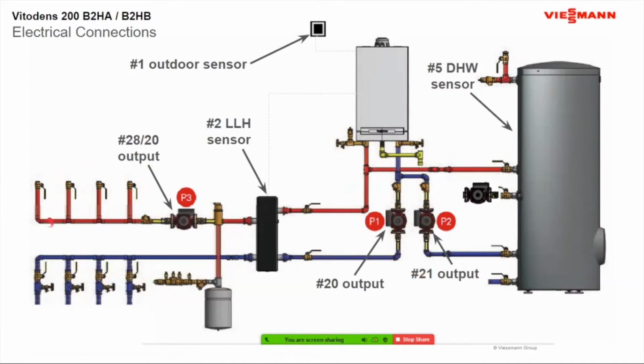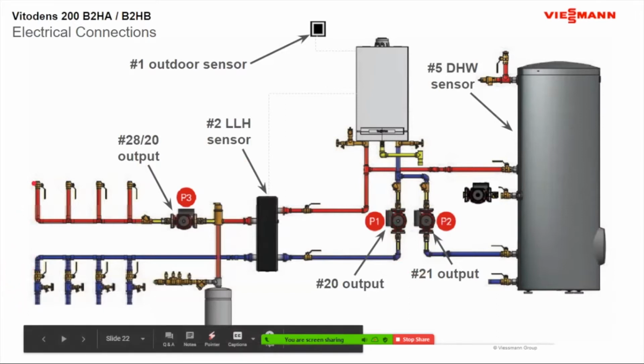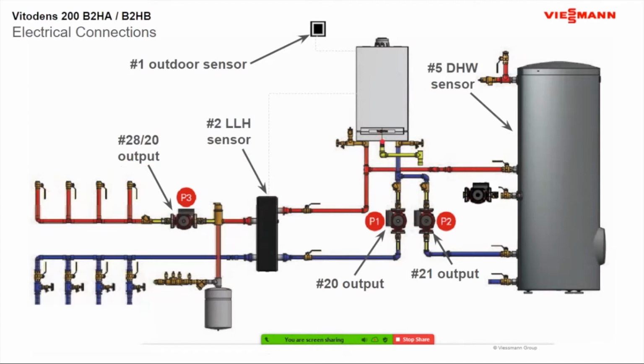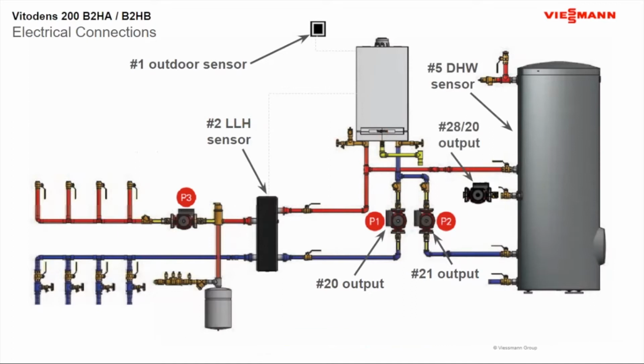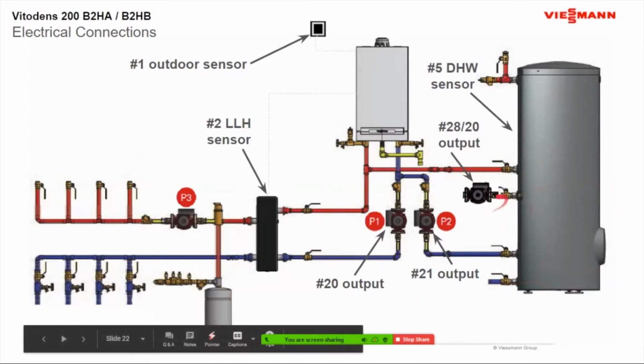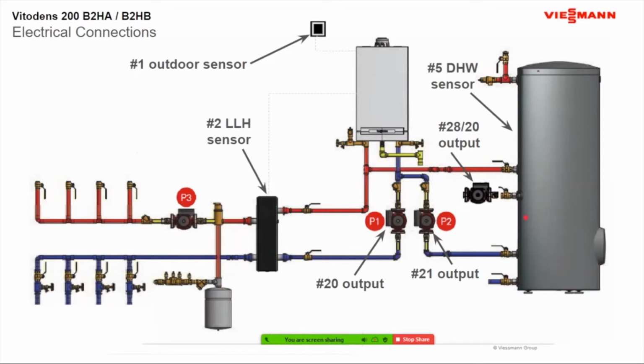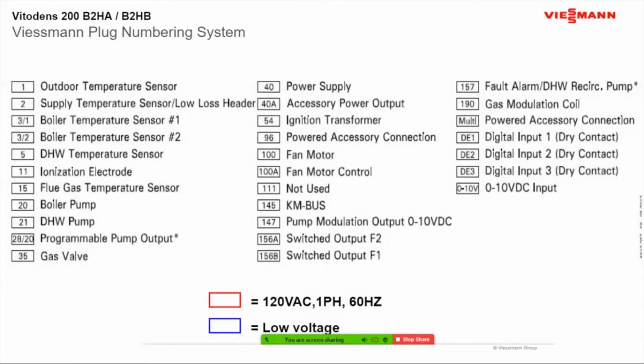So if you are on this side, say you've got these two here going out to your indirect tank, you now have to tell your boiler through coding 5B and domestic that you're on this side of your low loss header. It's pretty simple to do. You'll see once we get into coding as well. This is just showing where you might put all your sensors or your outputs, like your pump outputs. So remember that 2820 can be either domestic recirculation, which we have a recirculation tapping on all our indirect tanks for recirc. You can put one there as well, or you can make it a system pump.